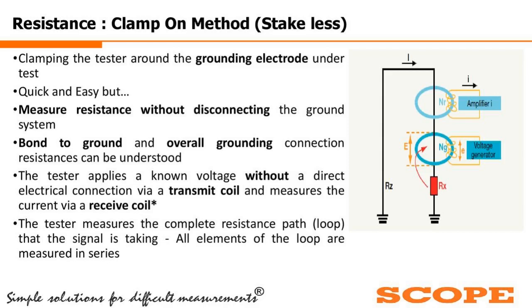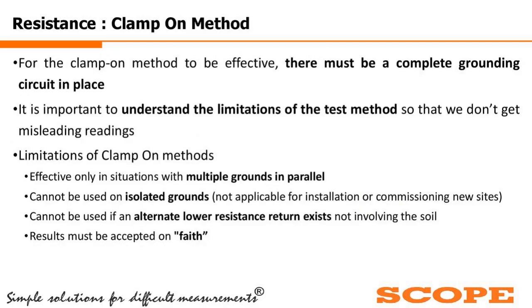So at least some elements, whatever elements are coming into the loop, will be considered, but at least I am not considering any stray currents passing in parallel; I will be able to eliminate those. However, the loop will come into the picture, whatever is in that electrical loop. So those are the major limitations of the clamp-on method. For the clamp-on method to be effective, there must be a complete grounding circuit in place. It has to be a complete circuit, otherwise the leakage current will not flow and no measurement will be possible. It is important to understand the limitations of the test method so that we don't get a misleading reading.